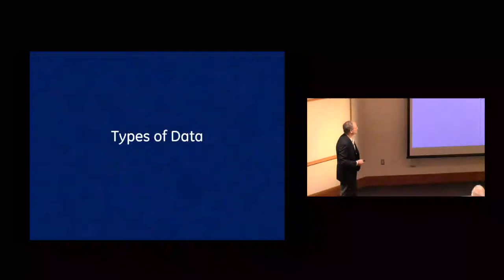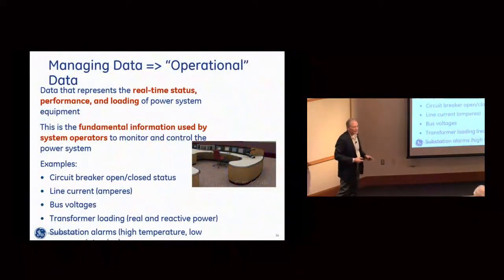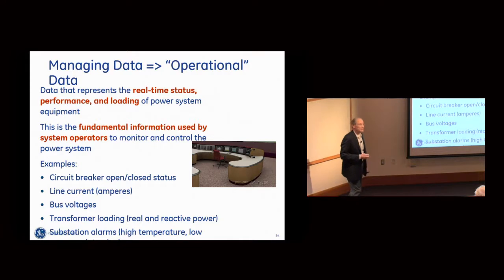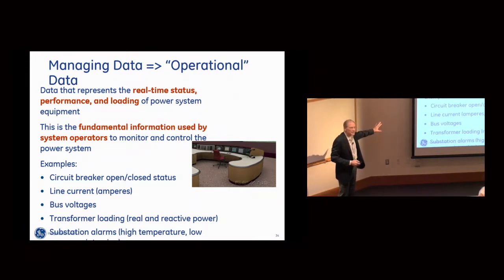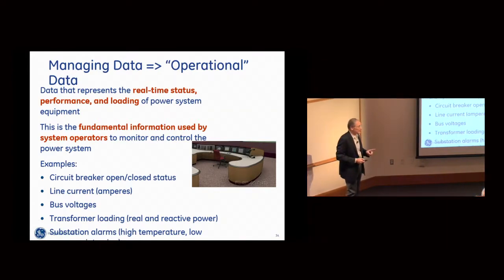I wrote an article in 2003 in IEEE Power and Energy Magazine introducing the concept of operational and non-operational data, because I was looking at these new IEDs and realized we can't manage all the data as if it were the same. We typically only focused on the data that went to the control center, to the operators. But for IED vendors, the sexiness of an IED isn't the operational data — that's standard stuff. It's the non-operational data: digitized waveforms, sequence of events reports.